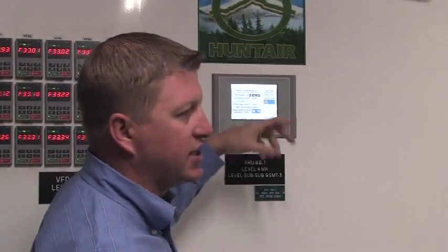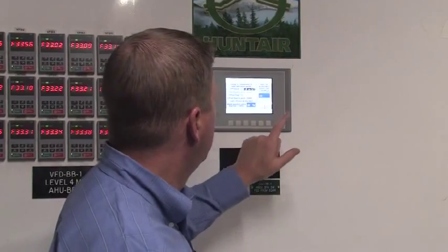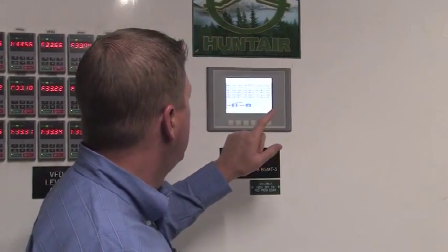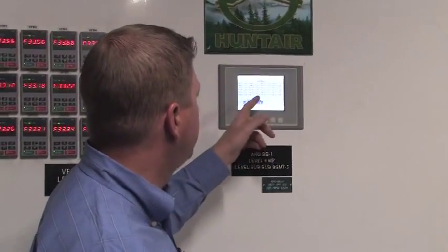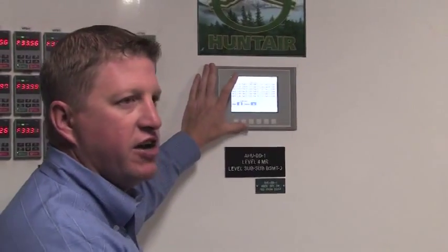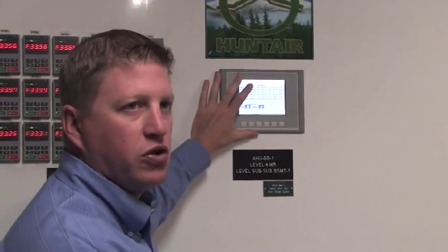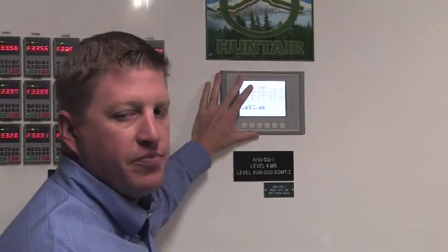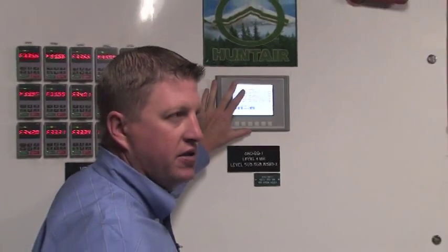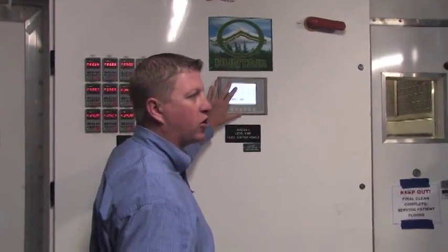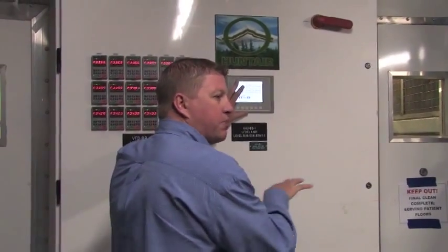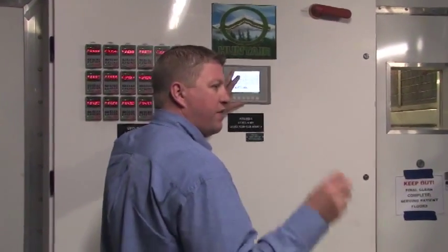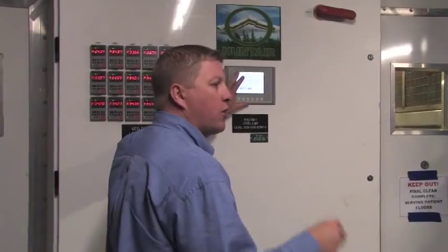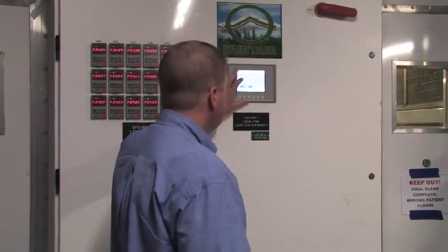Airflow adjustment, that's to adjust the K factor on the airflow stations. Here's the outputs for all the transducers. Each individual fan actually has an airflow station to it. Through the LonWorks integration, you can actually get the individual performance of each fan. If one fan were to fail, you could get an alarm point of that exact fan.